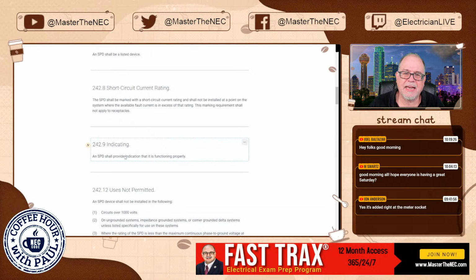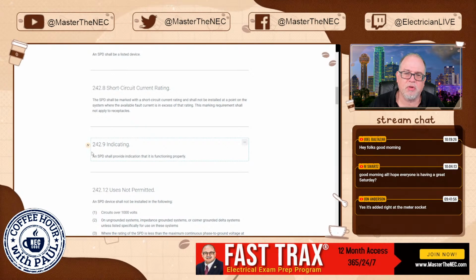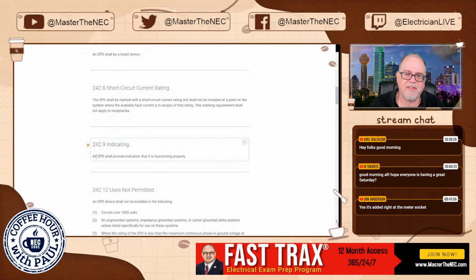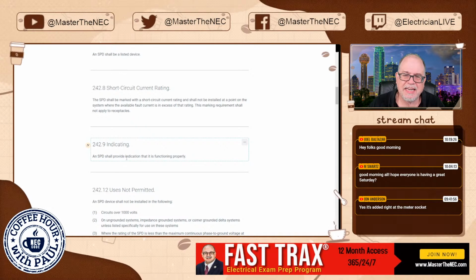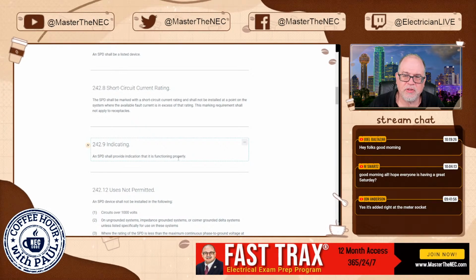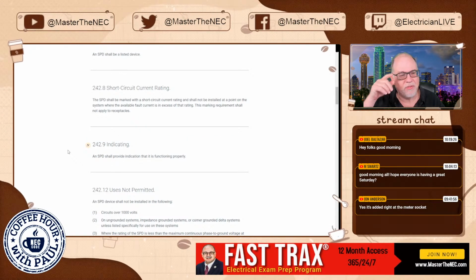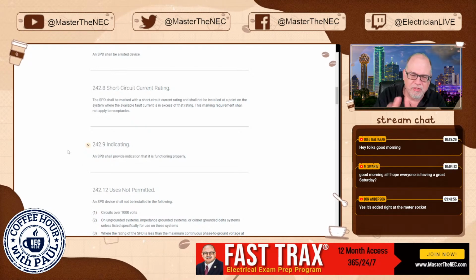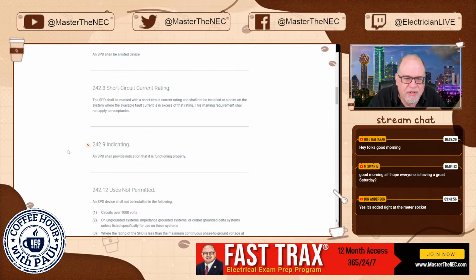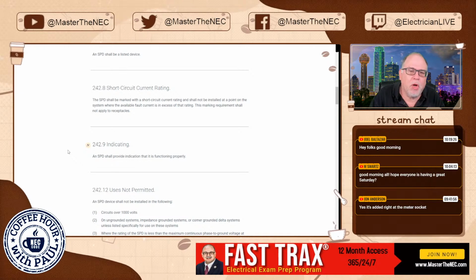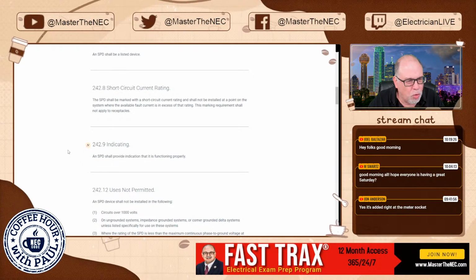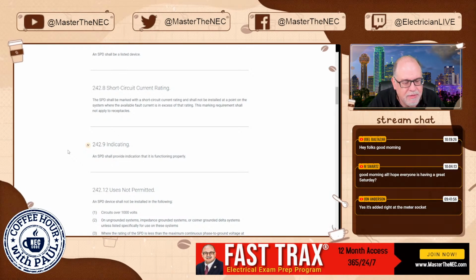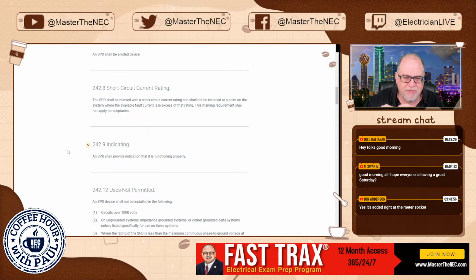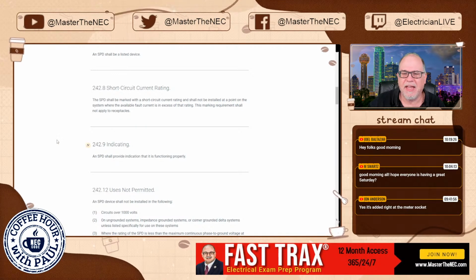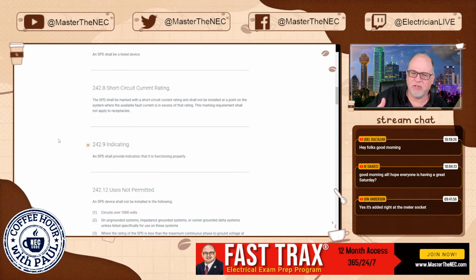Again, indicating, all right, so this is new, 242.9. It says an SPD shall provide indication that it is functioning properly. Now, this is something you're not going to worry about, since this rule wasn't in the 2020, most of the manufacturers of these had lights on them, but maybe not all of them did. Now the rule is, and this is something the manufacturers are going to take care of, they have to have a light on there that tells you it's functioning properly.